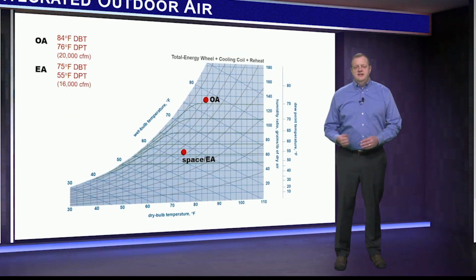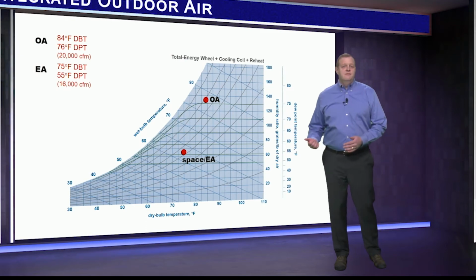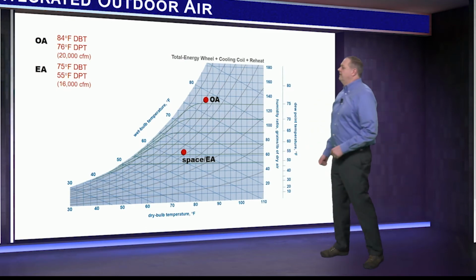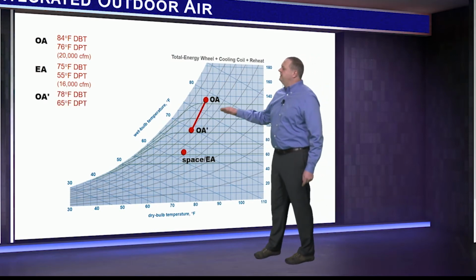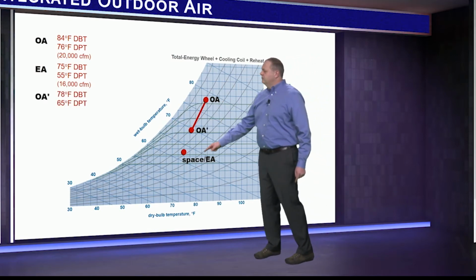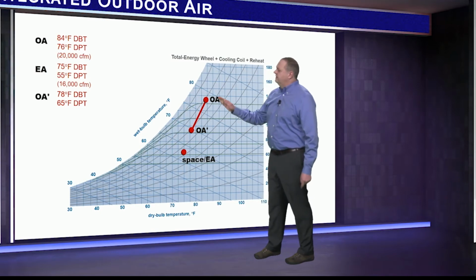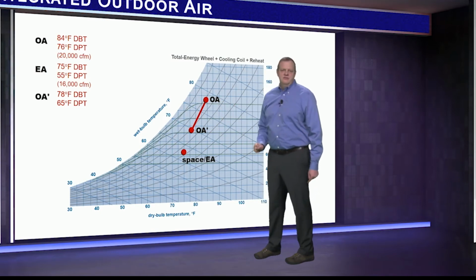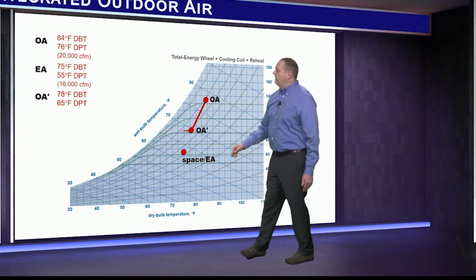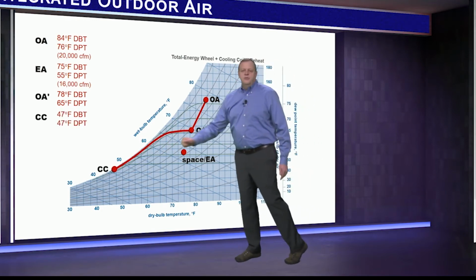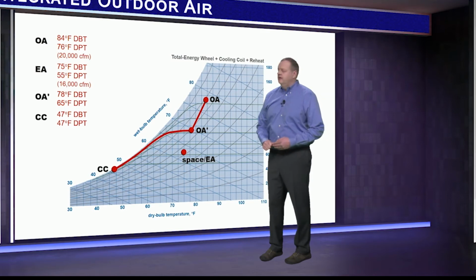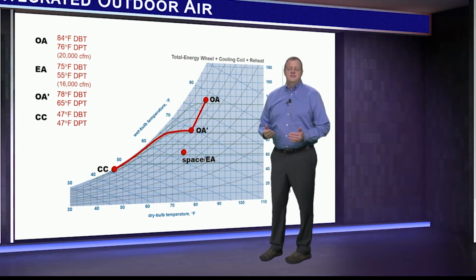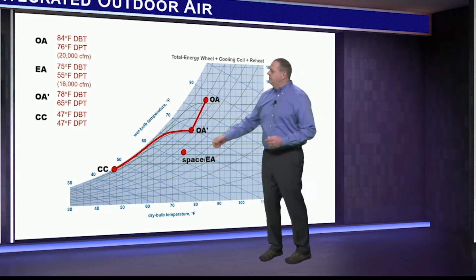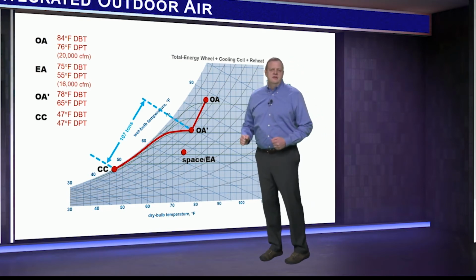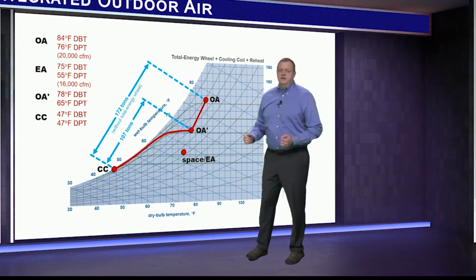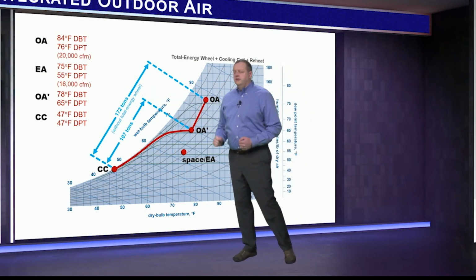Here's this unit depicted on a psych chart. This is an example of a warm, humid day. The total energy wheel transfers sensible heat and water vapor to this cooler, drier exhaust air stream. This reduces both the cooling and dehumidification loads. The cooling coil then dehumidifies this air to the required 47-degree dew point. Now in this example, we're conditioning 20,000 CFM of outdoor air. So the load in the coil is 107 tons. Note that if we didn't use energy recovery, this load would have been 172 tons.